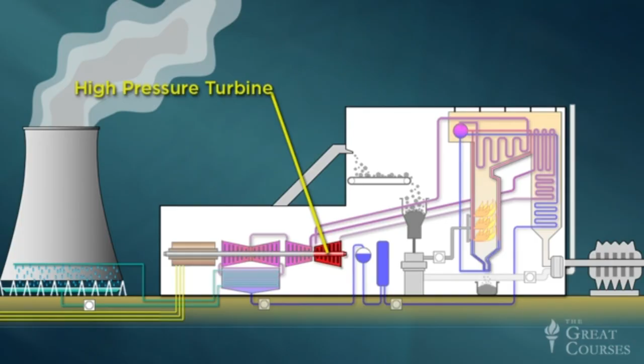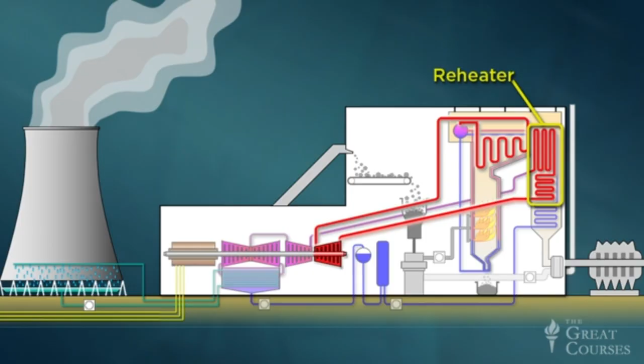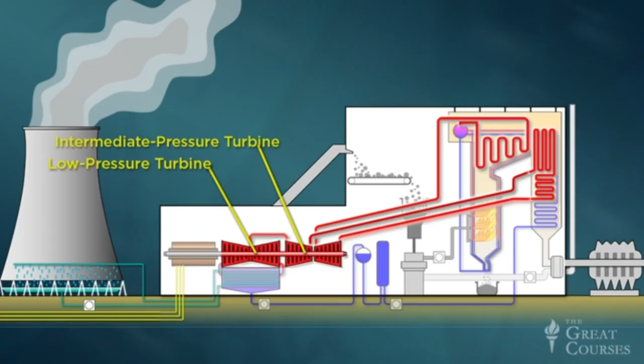The reheater transfers more waste heat from the flue gases into the steam, raising its temperature close to 1,000 degrees Fahrenheit, though not increasing its pressure appreciably. And now the steam is piped in succession to an intermediate pressure turbine and a low pressure turbine, which extract even more energy and transmit it to the rotating shaft. These 2 turbines must be physically larger than the high pressure turbine because lower pressure steam occupies more volume. But together, these 2 larger machines actually account for only about 40% of the kinetic energy imparted to the shaft. The smaller high-pressure turbine actually does most of the heavy lifting.